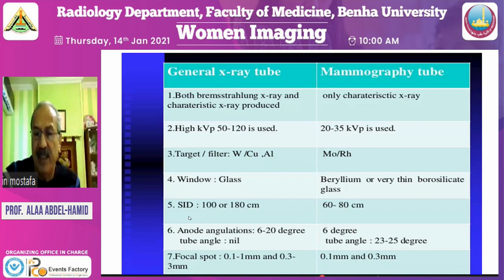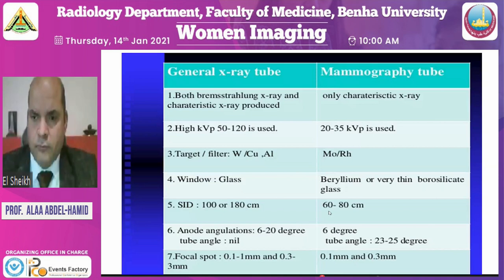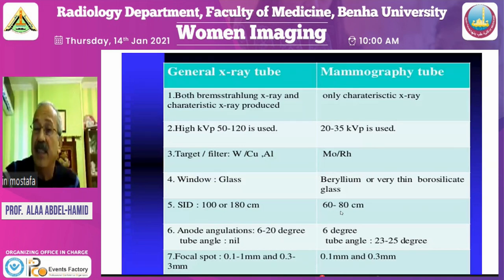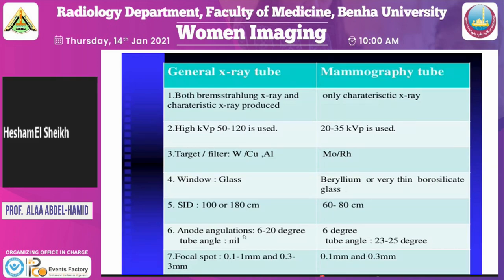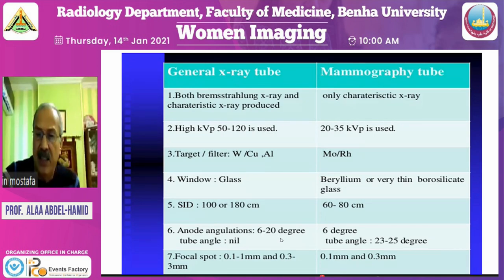The source film distance in the general X-ray tube is long. It is either 100 to 180 centimeters, but in mammography, it is from 60 to 80 centimeters, and it is a fixed distance. You cannot change the distance between the target and the film. The tilt angulation in the general X-ray tube is 6 to 20 degrees, but that of the mammographic tube is 23 to 25, and we'll explain this later. We have different focal spots, 0.1 to 1 millimeter in the general X-ray tube, but in mammography, it is very small, 0.1 to 0.3 millimeter.